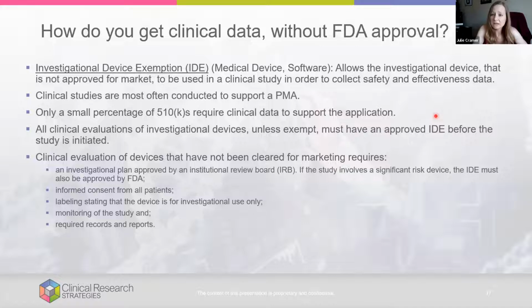If it is a significant risk device, then the IDE also must be approved by the FDA. It must have informed consent for all patients, and labeling stating that it is an investigational device for investigational use only. The study requires monitoring, as you would for any other clinical study, and requires records and reports. And then this type of clinical study that you perform under an IDE is where you get the clinical data to support your PMA application.